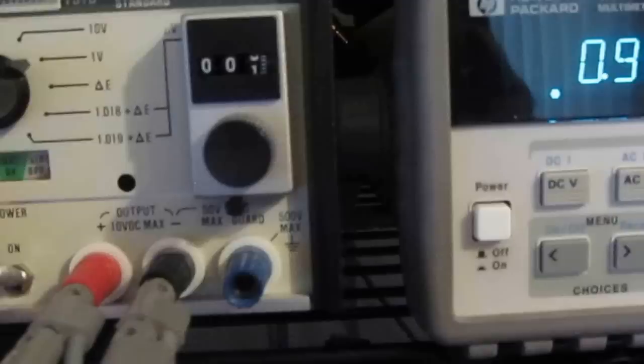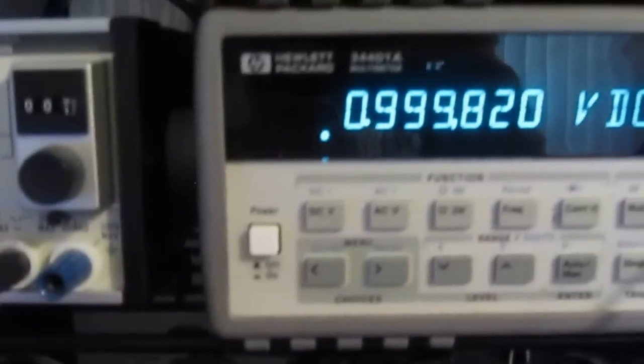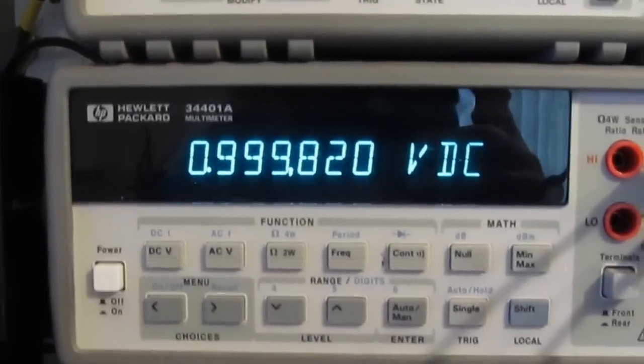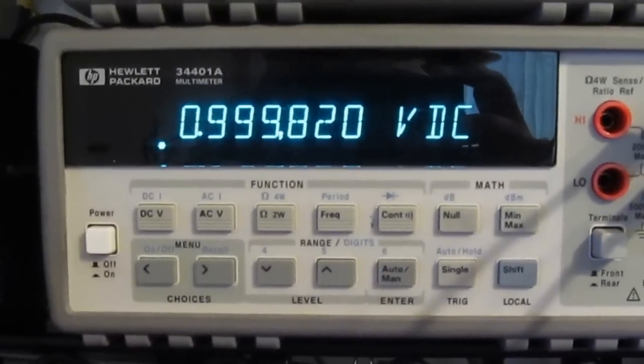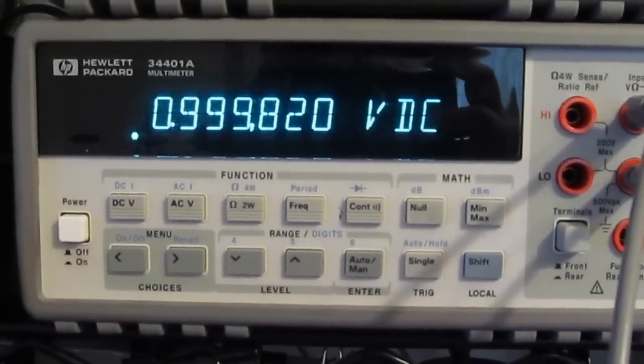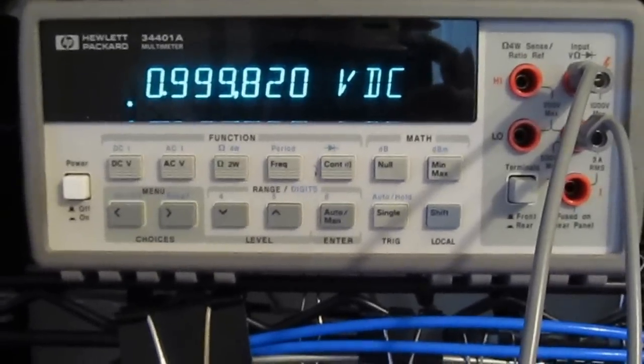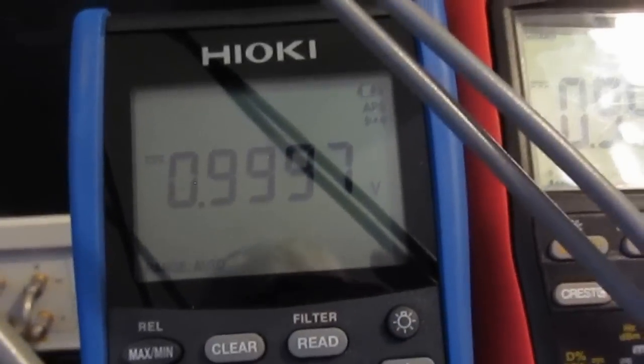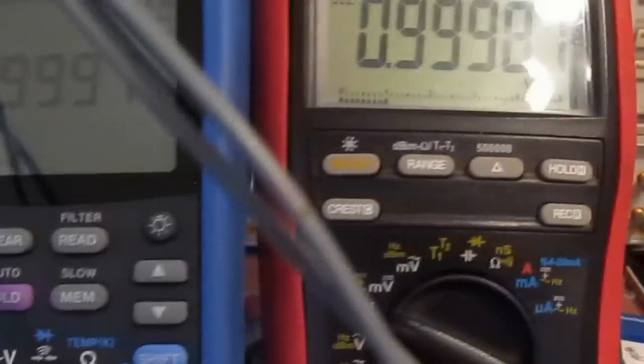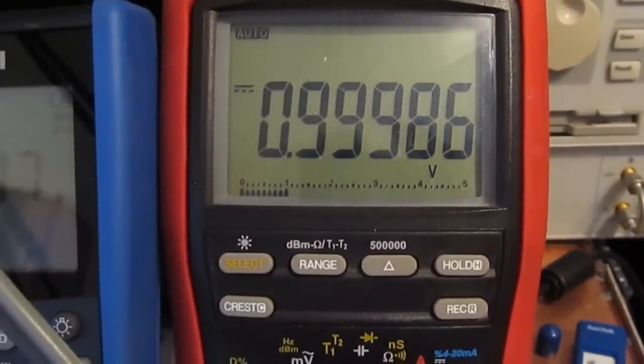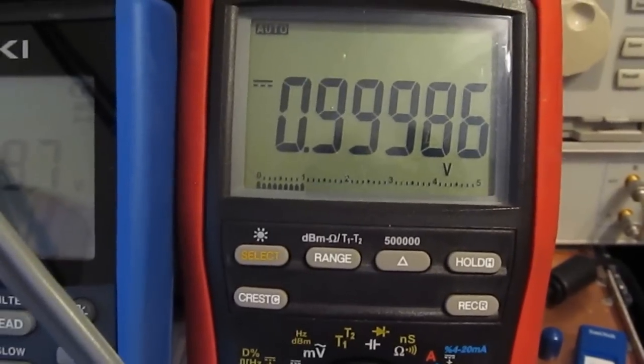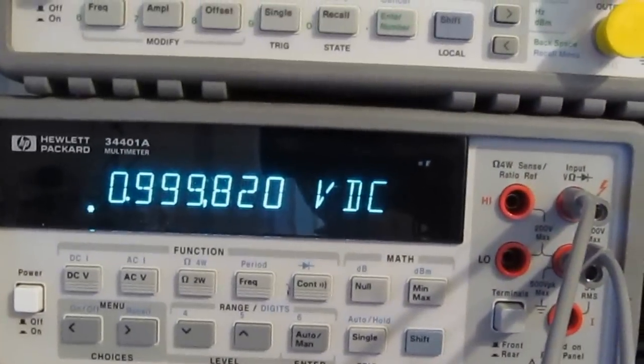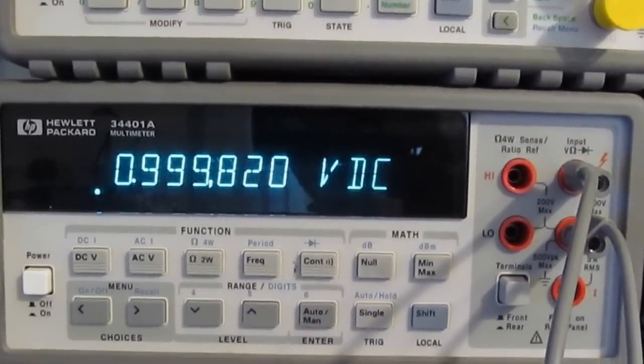Here I have my Fluke 731 reference standard. This is currently set for 1 volt, and it's attached to our HP34401A. You can see it's reading 0.999820, and that's with all 3 meters attached in parallel. So here's our Hioki DT4282 at 0.9997. And here's our Brymen BM869s at 0.99986. So that Brymen is actually quite close to our old HP meter.